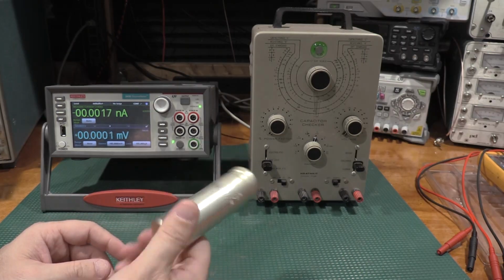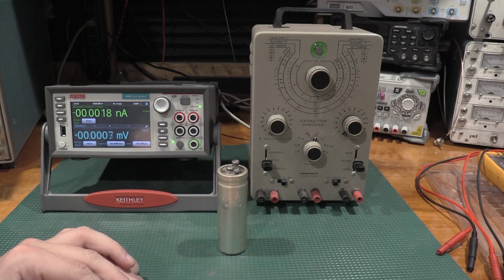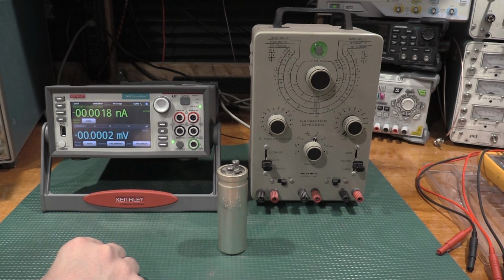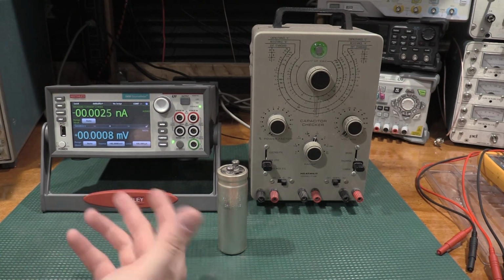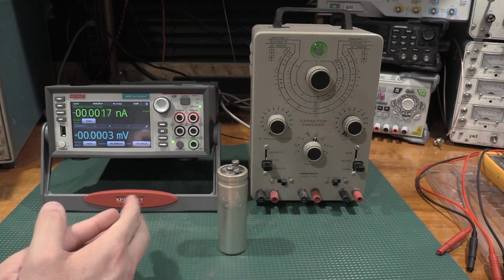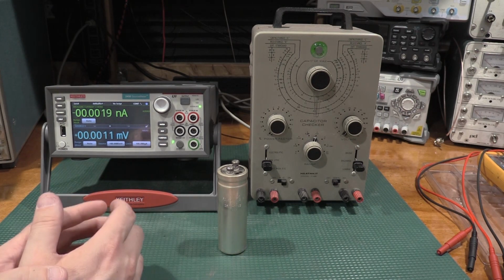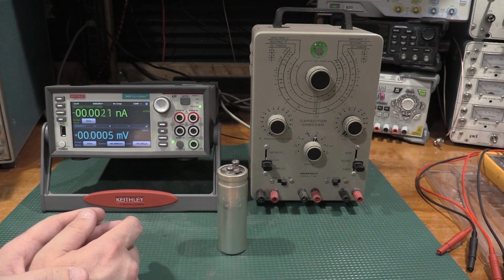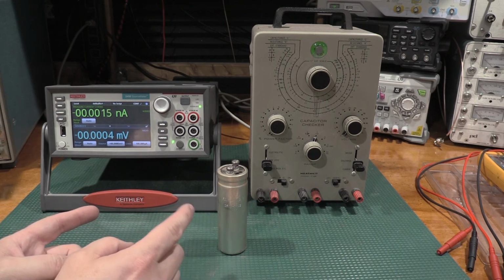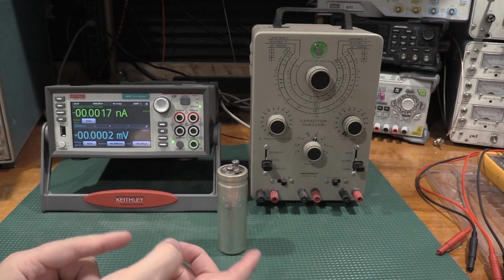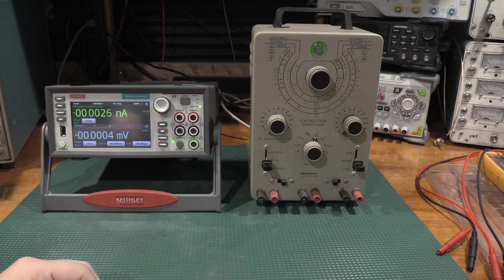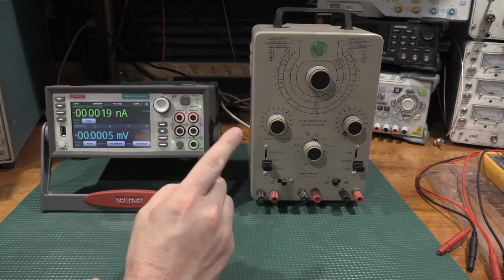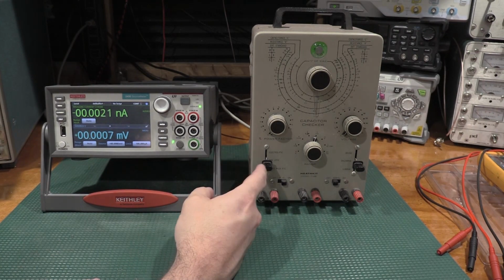So all capacitors, regardless of type, regardless of make, regardless of vintage, regardless of anything, will exhibit some leakage. They're real components. They will leak some DC through them. Everybody says they're ideal, things like that. They're not. Some will get through. Now, how good the capacitor is depends on how much of that some gets through. And that's actually the first thing we want to get into, is how does this thing actually test capacitors and read them? It's current based.